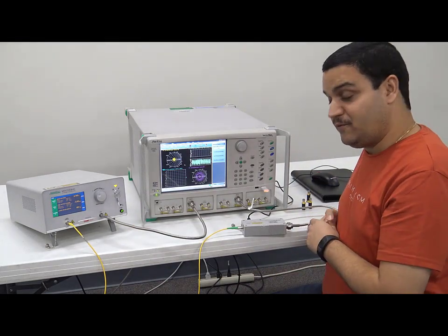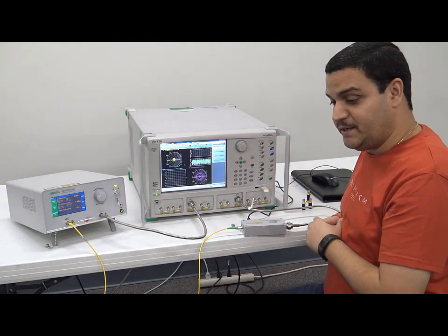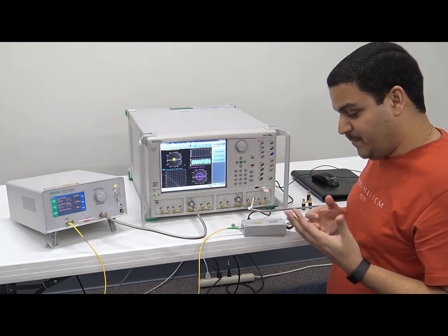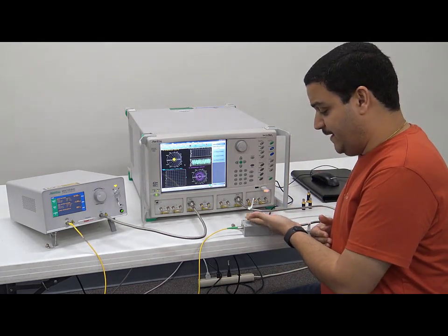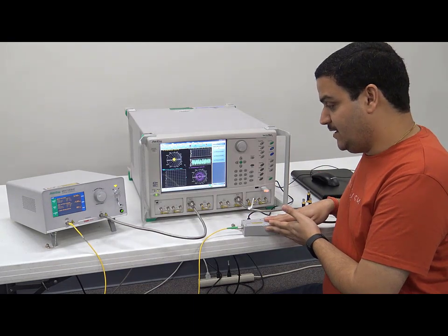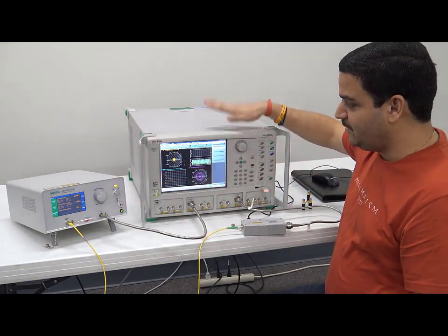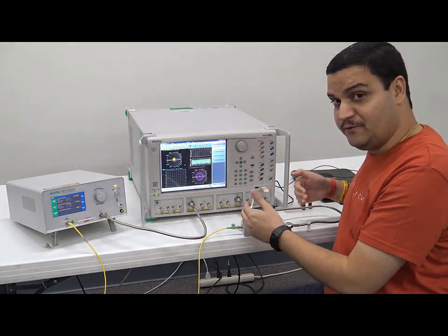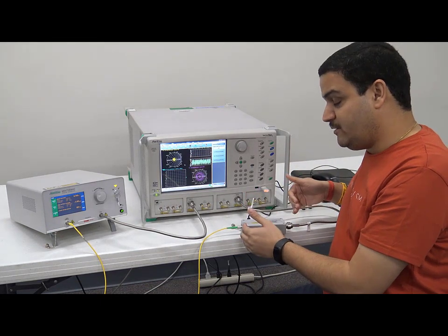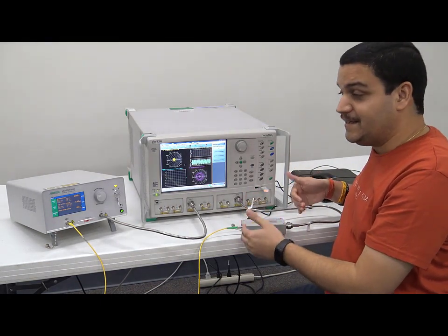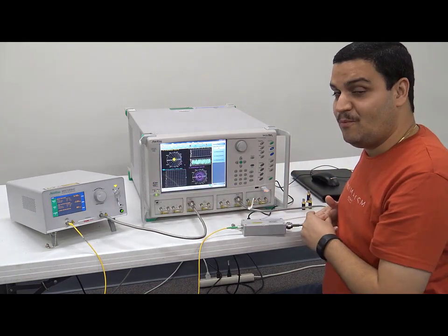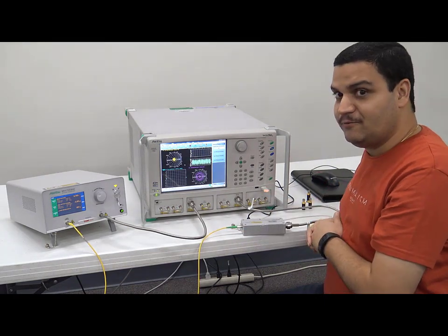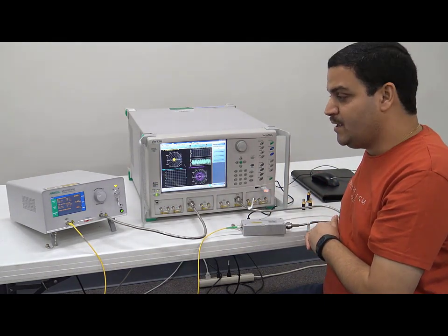Now, in the next step, if you want to characterize any of your own photodetectors or ROSA kind of devices, you can disconnect these two ports, take this out, and then put your own photodetector in place of this standard photodetector. Now, because you have the S2P file of that, you have the RF cal of that, now you can de-embed these two, and then the response will be of your photodetector. Again, the NIST traceability is going to be there because in the initial step, you characterized your EO modulator using the NIST OE photodetector from us. So this is going to be the workflow of my demo today.